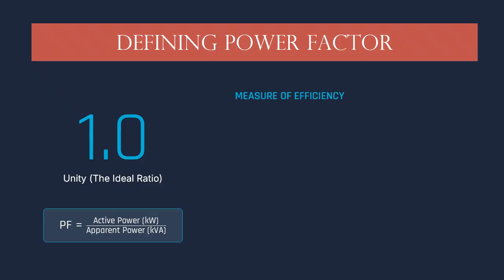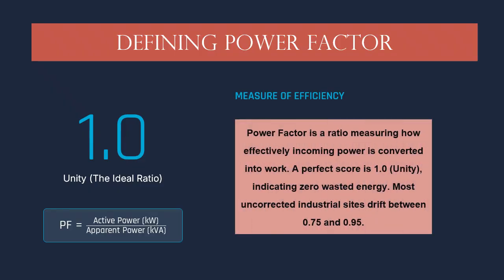Defining power factor. This brings us to the core metric, power factor. Simply put, it is the ratio of working power to the total apparent power flowing through your system. The ideal score is 1.0, or unity, which means zero wasted energy. However, in most uncorrected industrial sites, this number drifts down between 0.75 and 0.95, indicating a significant leak in efficiency.